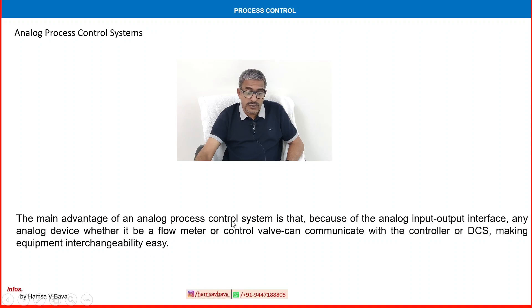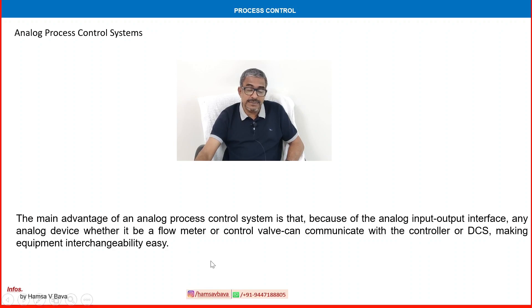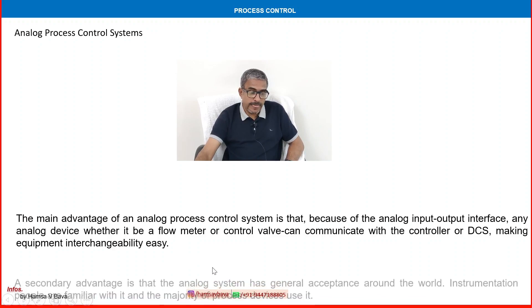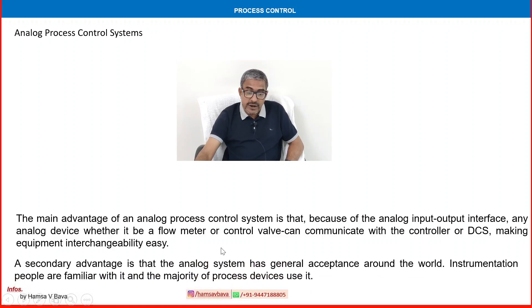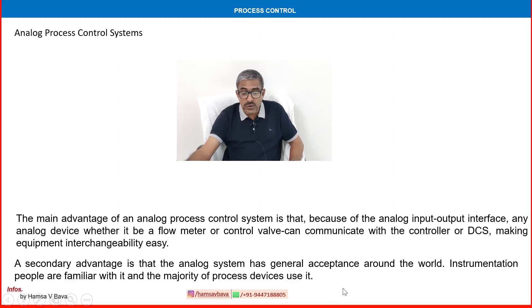The main advantage of an analog process control system is that because of the analog input-output interface, any analog device — whether a flow meter or a control valve — can communicate with the controller or DCS, making equipment interchangeability easy. A secondary advantage is that analog systems have general acceptance around the world; instrumentation people are familiar with them, and the majority of process devices use them.